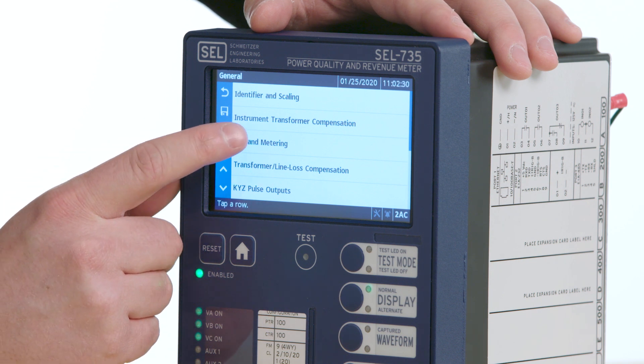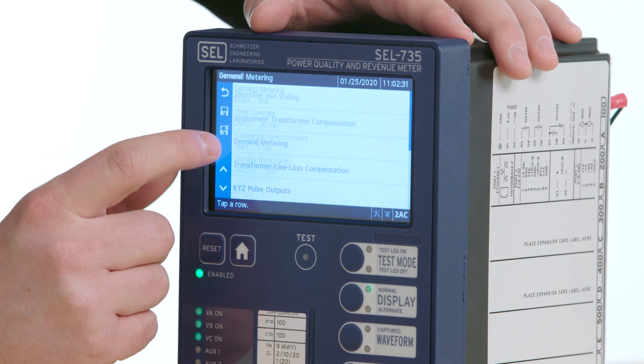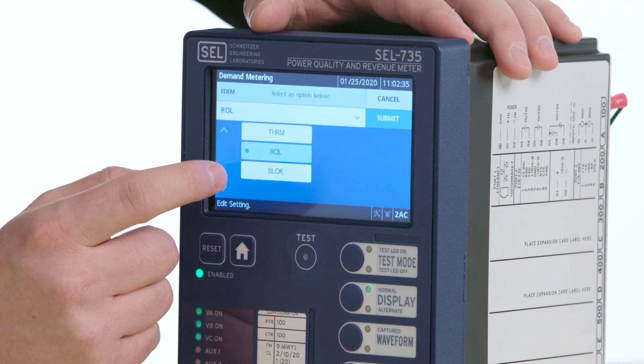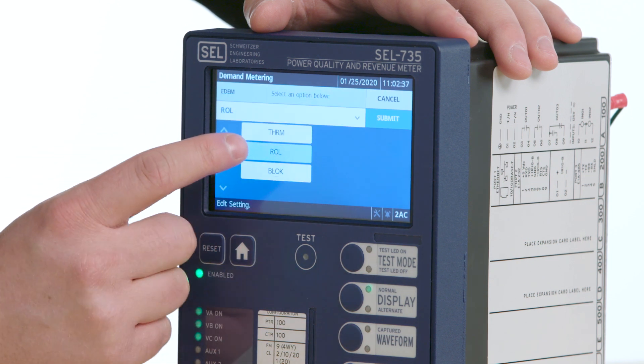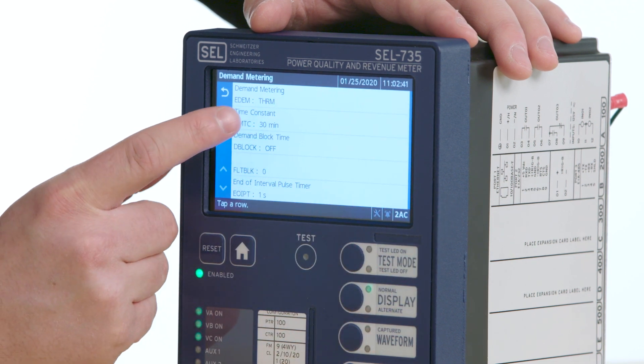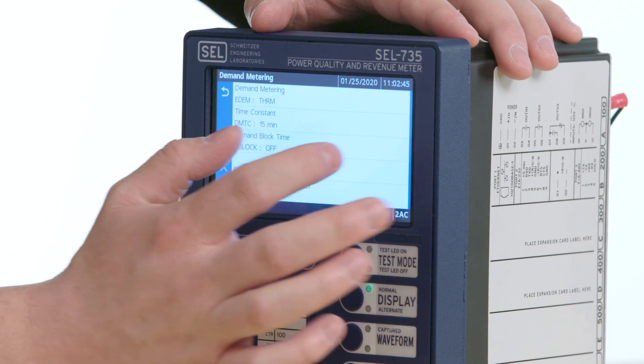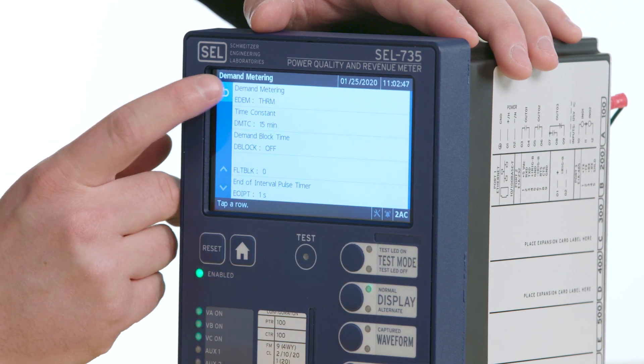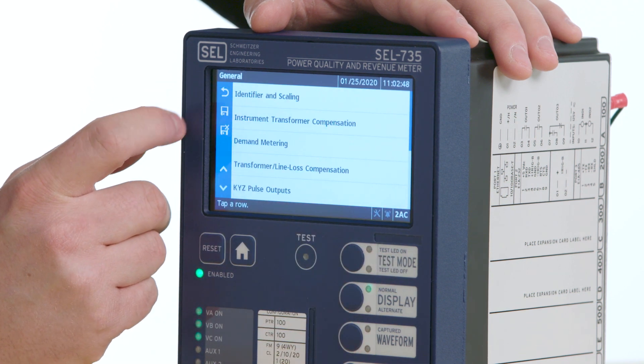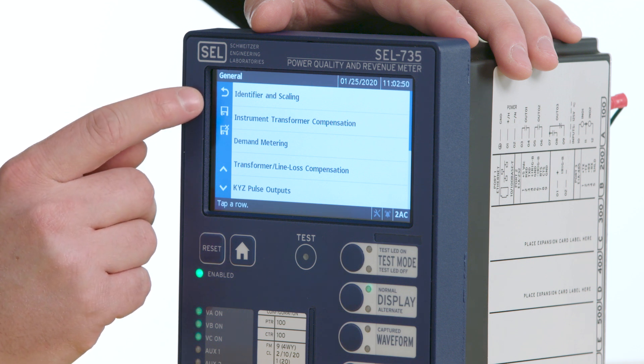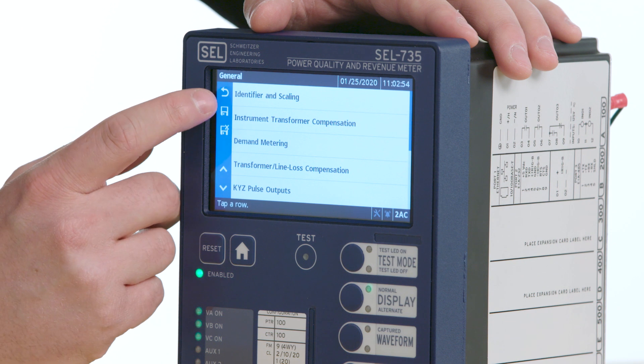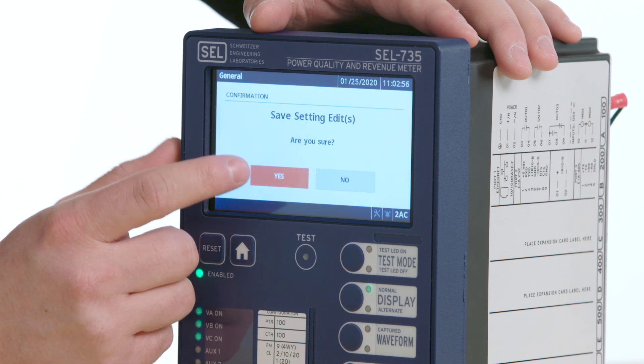Next, I will change the demand metering settings. For this application, I would like to use thermal demand metering with a time constant of 15 minutes. Upon hitting the back button, I will have the save and discard icons, and I would like to save these new settings.